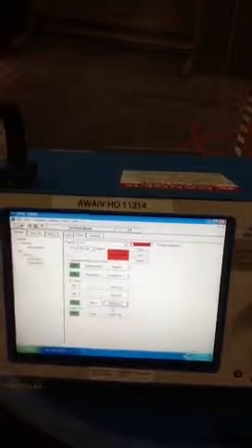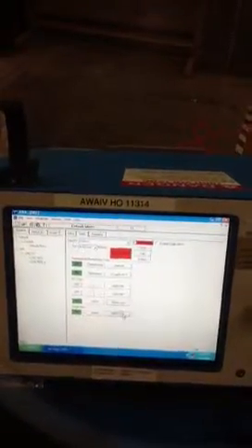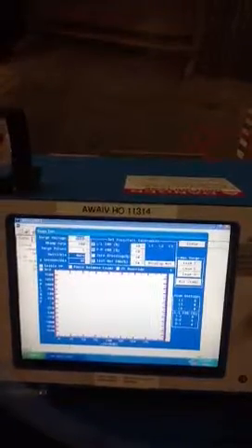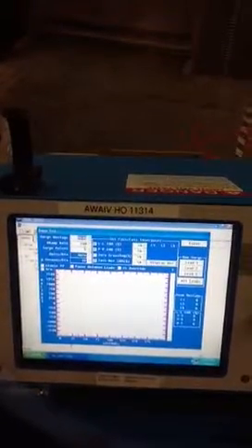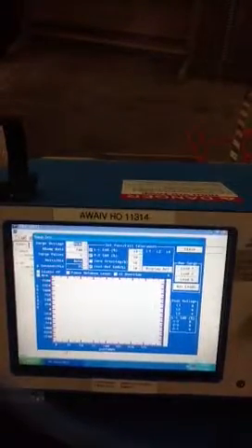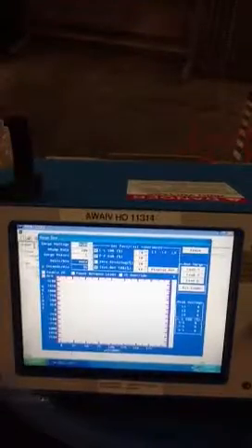Go to close, and then we're going to go to our surge test. First thing we're going to do is set our voltage, our ramp rate, and our pulse width, and if you want to, you can set your microseconds per division to automatic, or you can set it as a particular value. I'm going to leave it at this value.